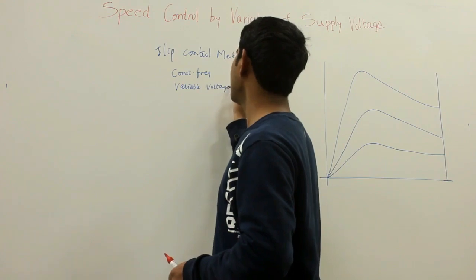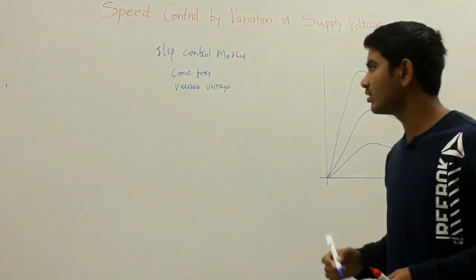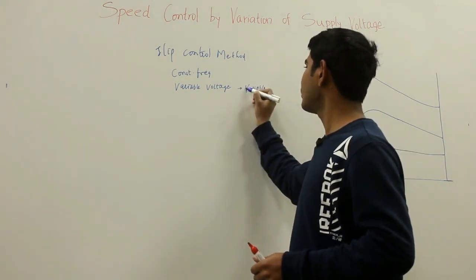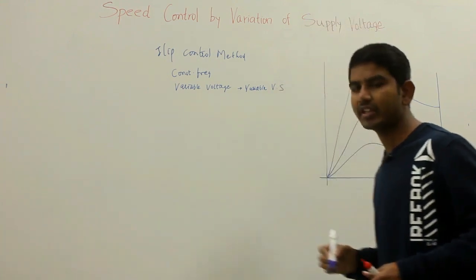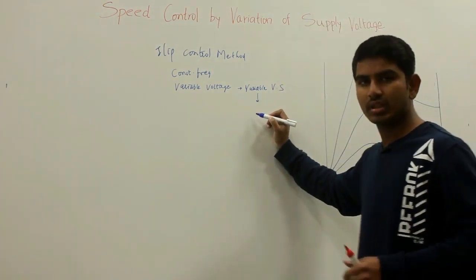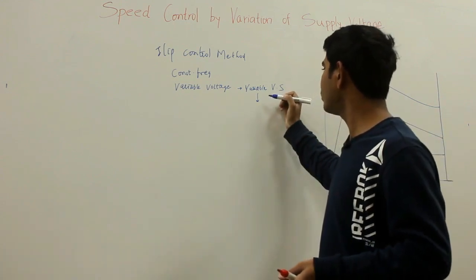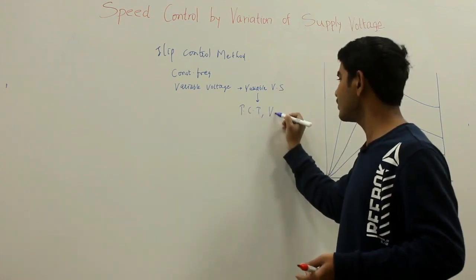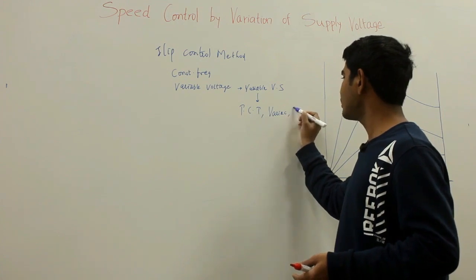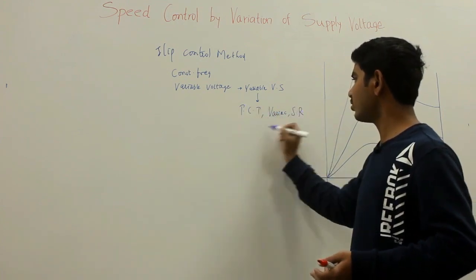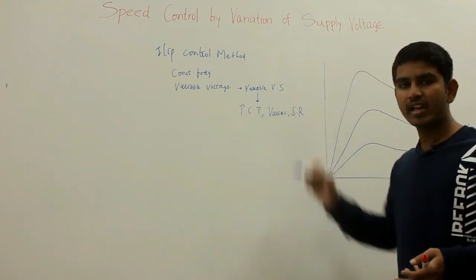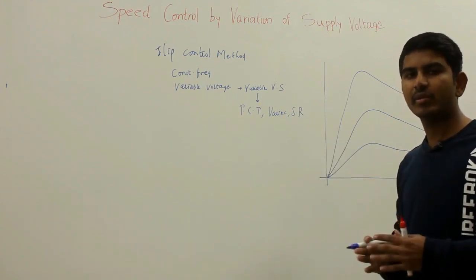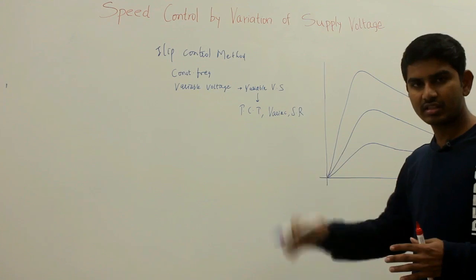By varying the supply voltage, you can vary the speed. We need a variable voltage source for using this method of speed control. This variable voltage source can be obtained from tap changing transformers, variable transformers, or saturable reactors. By using this auxiliary equipment, you can get the variable supply voltage. In general, this method of speed control has various limitations.